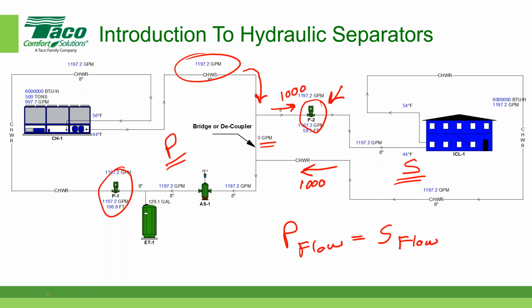The second case, oh, and let's just think in terms of the temperature. Let's assume that the water temperature is 44 degrees Fahrenheit coming in this direction. That means it peels off and it goes to our load at 44. That's what that number represents. Over on the right side, let's say it comes back at 54, and so we get 54 degrees Fahrenheit over here. Kind of ignore these temperatures over here because they don't really apply to our little simplified example.